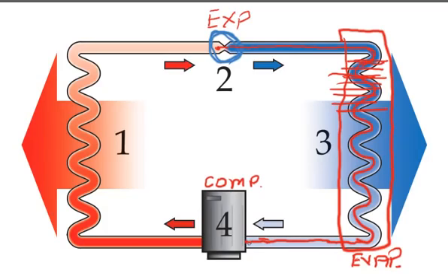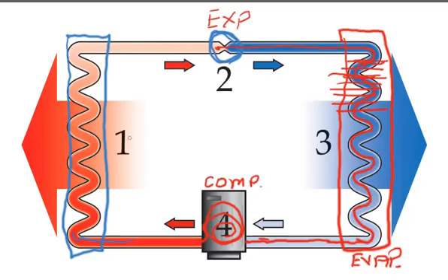So the pump is sucking this gas in, and what the compressor or pump does is it compresses or pumps this gas up into a high pressure gas, and this high pressure gas picks up heat as it goes through the compressor and comes out through this copper line and enters what we call the condenser coil. And the condenser coil is similar to the evaporator coil in that its job is to dissipate the heat. So it's also got lots of aluminum fins attached to it to help expand the surface area, and the air blows over this coil and blows the heat out of it.